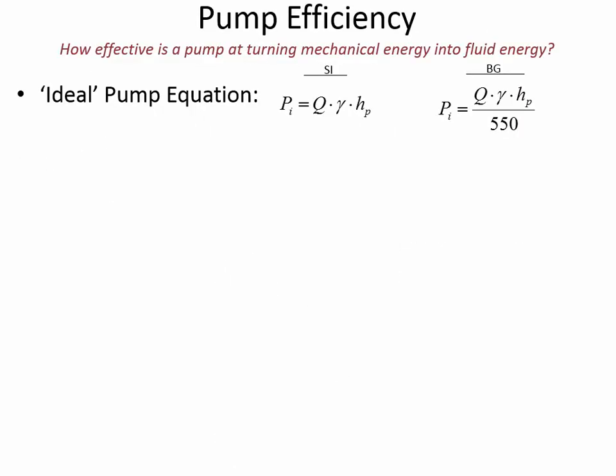That's a good question. All right, so you're going to need to know about efficiency in the homework, and ideally, the power required to move water can be calculated by this equation. In SI units, it's the flow rate in cubic meters per second, the unit weight in newtons per cubic meter, and then the pump head in meters. And so if you multiply those three terms together, what you'll get is the power in watts.